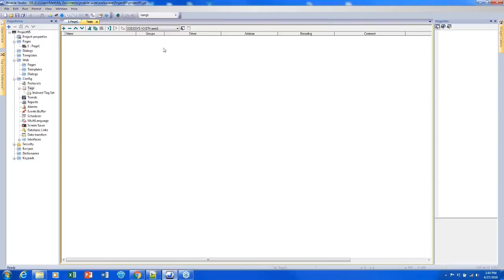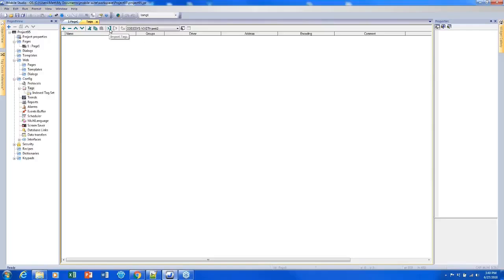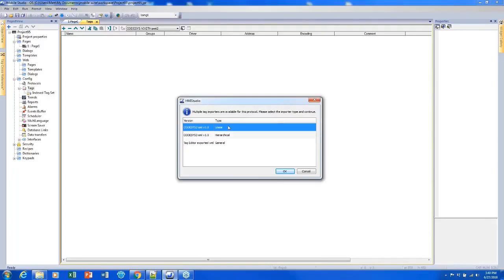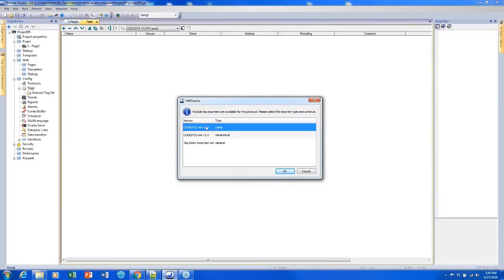For example if it's a Compact Logix PLC it would be L5K or L5X or something like that. In order to actually import that file we need to click on this icon here with the arrow in the bracket, import tags, and this will give us a pop-up showing which types of files we can handle. For Codesys we're only able to enter XML files which is fine because that's the only thing Codesys will export.